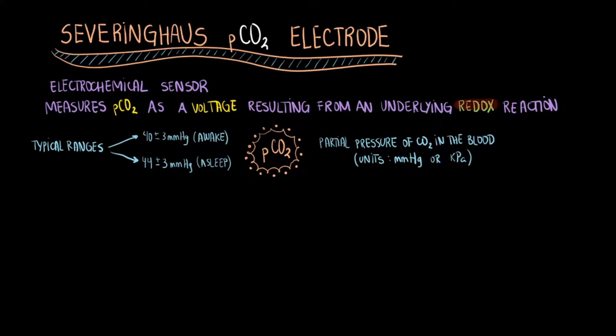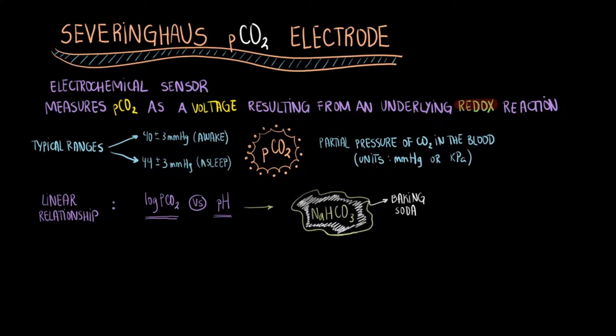In the Severinghaus electrode, a linear relationship between the log of PCO2 and pH is used to determine the partial pressure of CO2 in the blood. This is performed using a saturated solution of sodium bicarbonate, or NaHCO3, that is, baking soda.